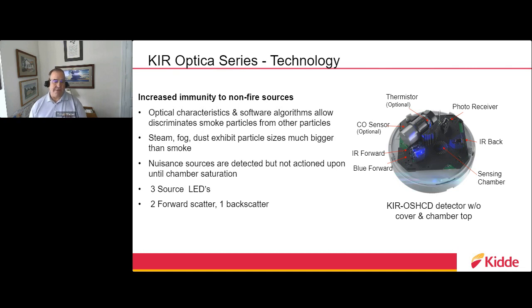The additional piece we've engineered into our product is extra LEDs: one infrared forward-scattering LED, one infrared backward-scattering LED, and a blue forward LED. These three different LEDs look at the smoke particles, determining size, shape, and density, running that information through an algorithm—all happening in split seconds—to determine if the particles in the chamber truly warrant a smoke detection alarm. That's what's happening inside the head.